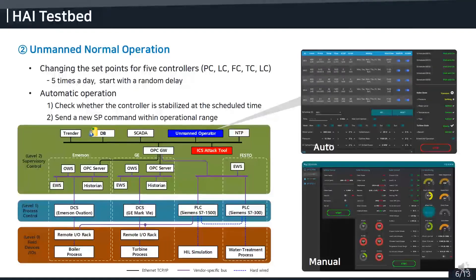The HAI testbeds are automatically operated to minimize human intervention. For five process controllers, their setpoints were automatically changed five times a day with a random delay. The automation tool checked whether the controller is stabilized before sending a new setpoint. If the system is settled, it sends a new setpoint command with a random value within the operation range. It is necessary to work experimentally to determine the safe operation range.